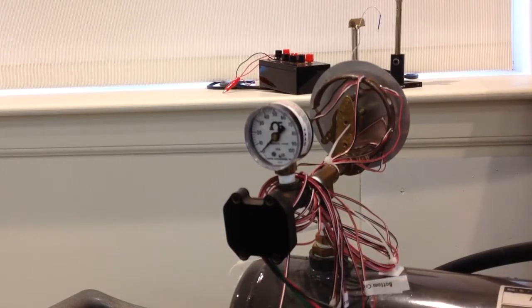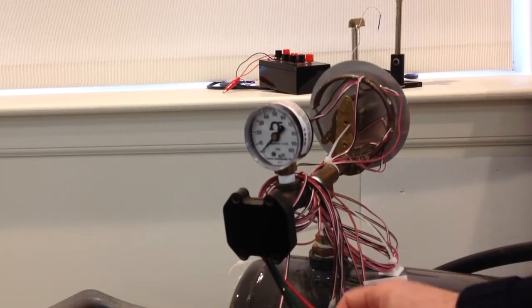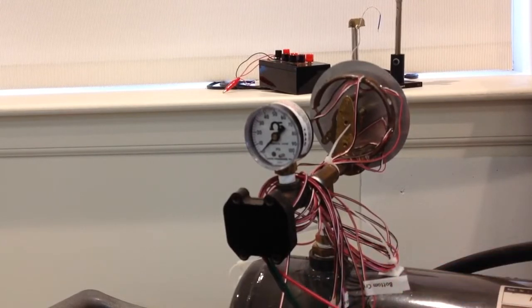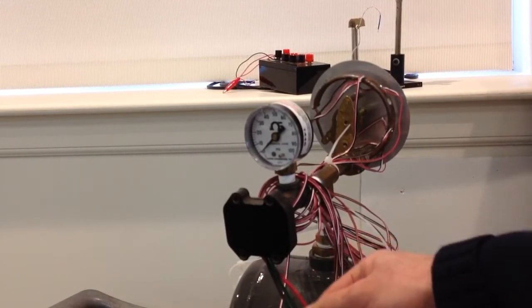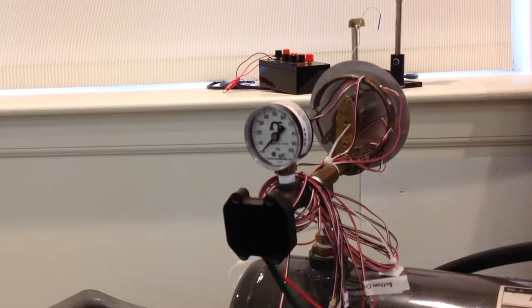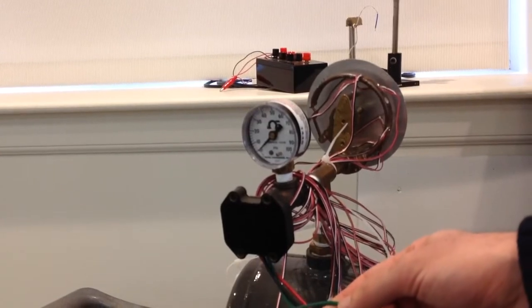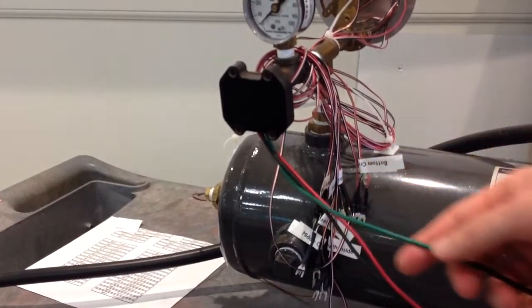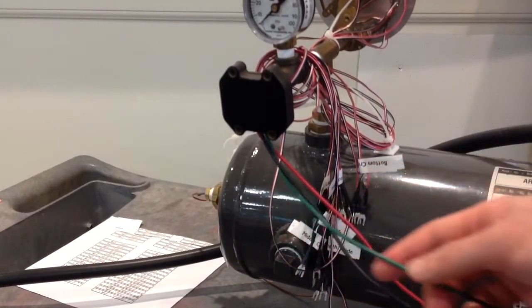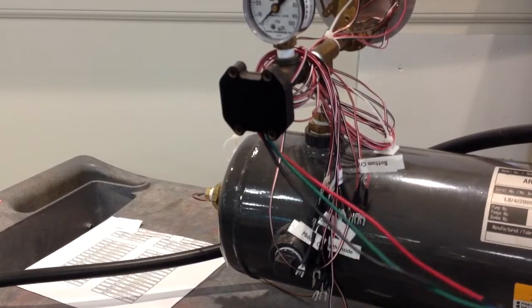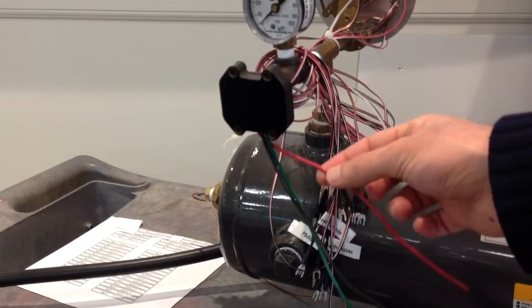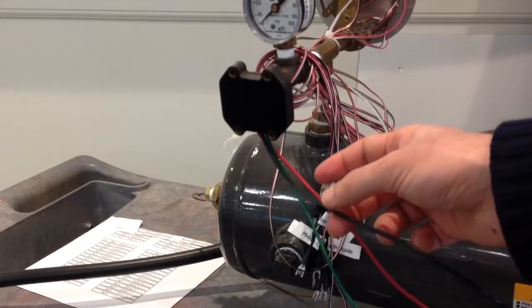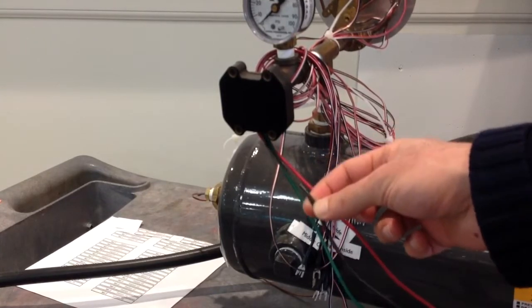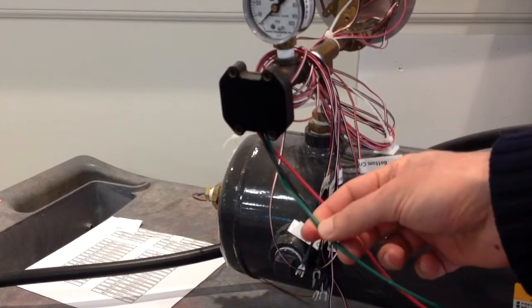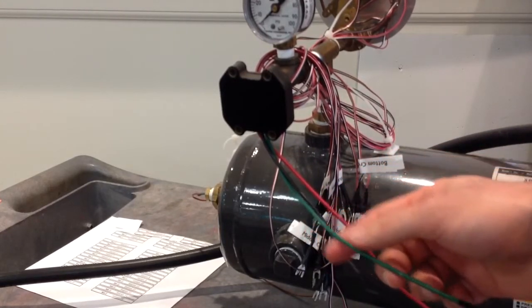Remember, one is ground, and we have one cable for excitation voltage. So this is supplying 8 volts to the pressure transducer. And then we have one cable that is for, so this yellow cable, the green cable is carrying the return signal from the pressure transducer. So we are going to excite 8 volts with this cable, use this as a ground, so everything is with reference to this cable. And this is where we read from the pressure transducer, okay?